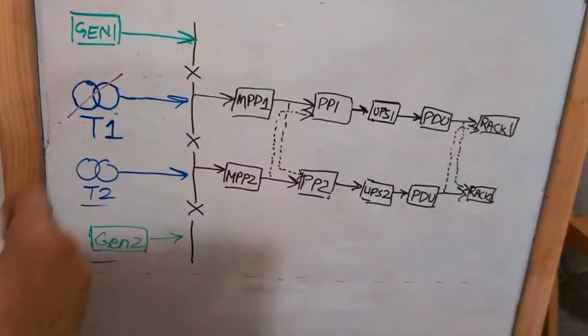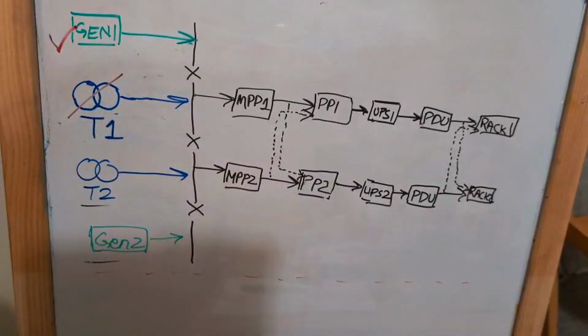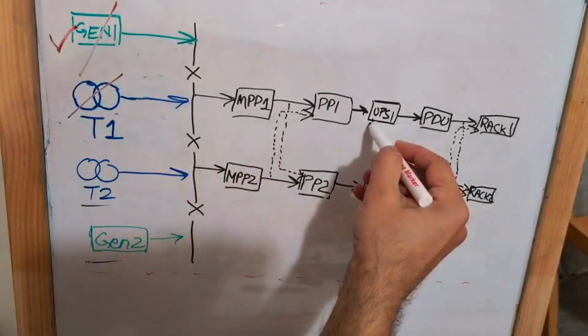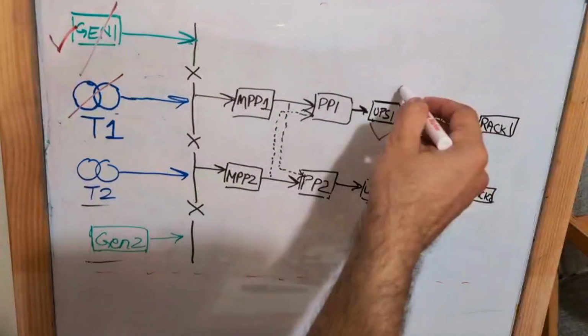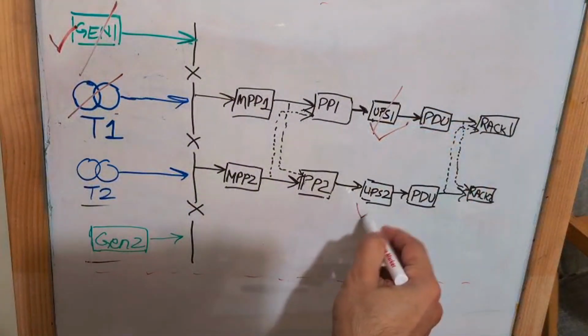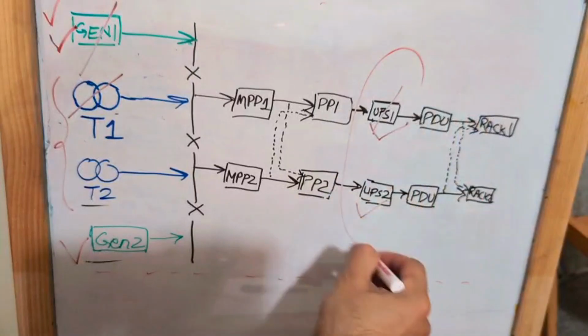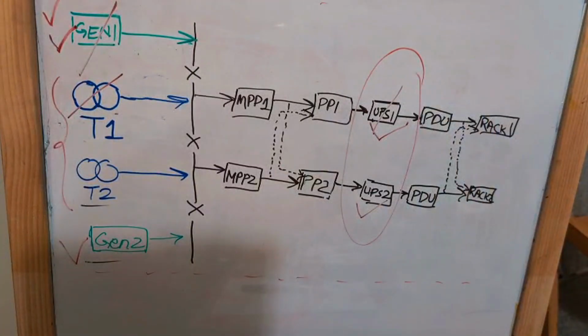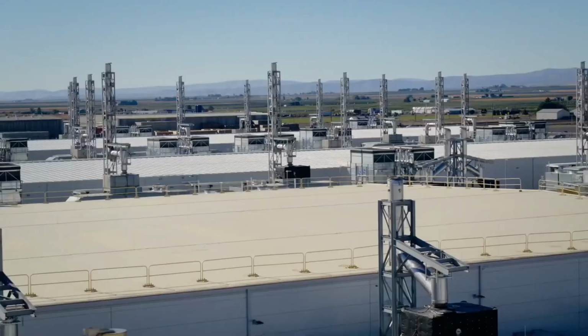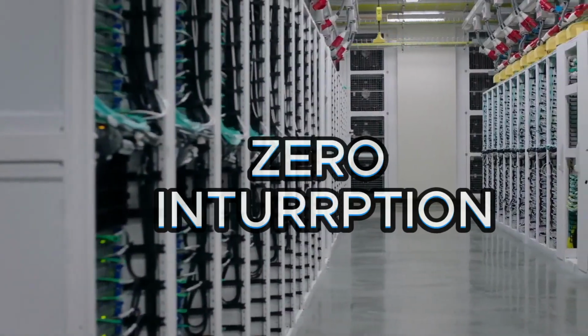So let's say a transformer goes down, no biggie, generator kicks in. If the generator fails, boom, UPSs are battery backed. And if the UPS unit has an issue, surprise twist, there's another UPS backing that one up. These UPSs also maintain quality of power into these racks. Redundancy on redundancy on redundancy. It's like a power relay race with no weak runners. Their goal, zero interruption, no risk, ever.